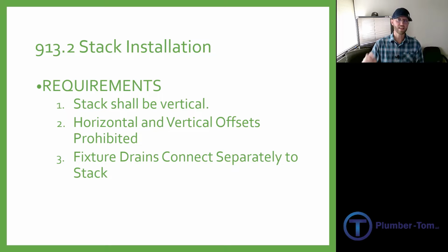Another requirement is that the fixture drains connect separately to that stack. Every trap has to be connected. And this is not for use for toilets or urinals. This is mainly just for other fixtures.